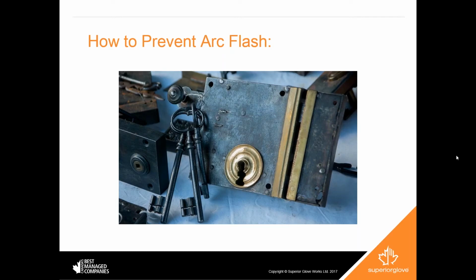How to prevent an arc flash? Probably the only foolproof way of doing this is making sure that your machine or piece of equipment is de-energized, i.e. that there's no power whatsoever coming to it. This way, there's just absolutely no way an arc flash can happen. But in the real world, that doesn't always happen.